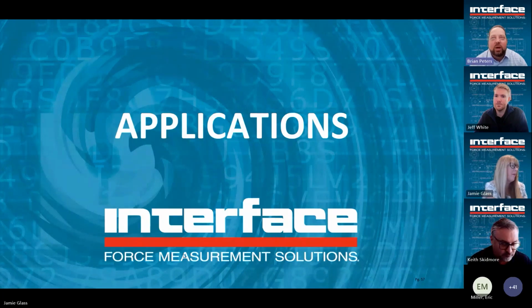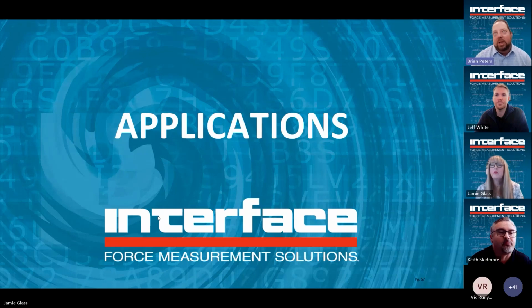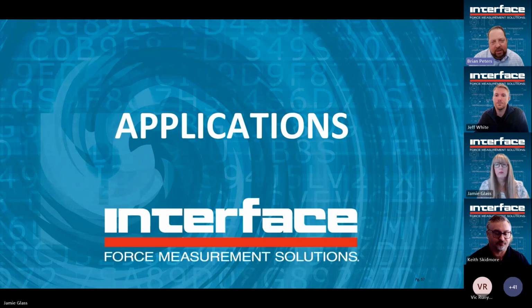Yeah, so good question. Like we talked about, where you can do some characterization, yes, we can offer span test data at elevated or cold temperatures. We have some limits in our hardware here, how cold we can go and how hot we can go, but absolutely, especially the IPCD that you all saw, that is absolutely tested at load at temperature as well. And when it's pressure tested, we also do pressure and temp sweeps to ensure that it meets the combined loading conditions. But yeah, if you're talking even a regular load cell and you have a high temp test, and you want to know how that load cell performs, we can absolutely do that testing.